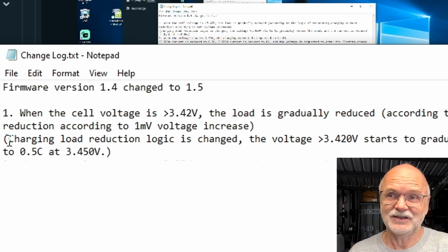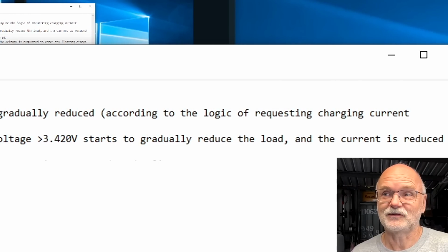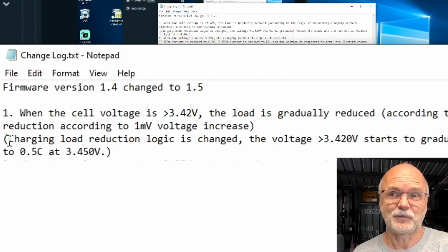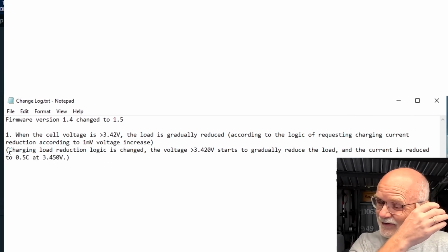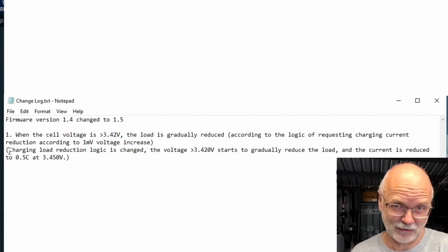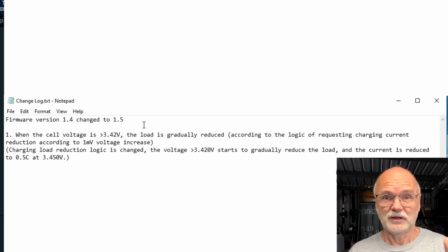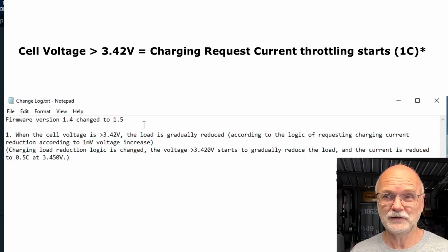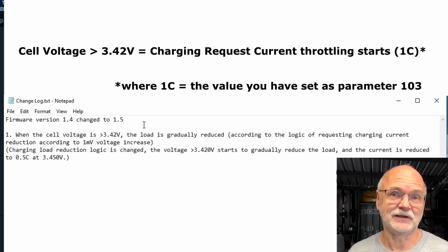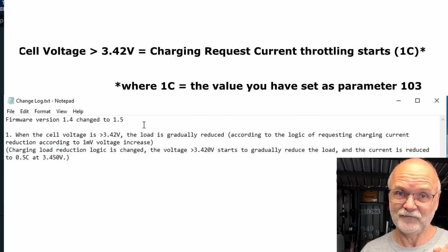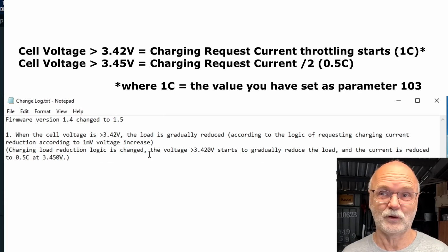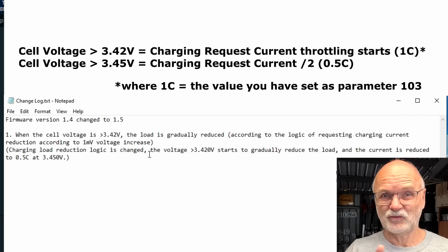Okay, bear with me here. The charging load reduction logic is changed. When the voltage is larger than 3.42 volts, it starts to gradually reduce the load, and the current is reduced to 0.5C at 3.45 volts. So what they're talking about is reducing the charge current into your battery - it's not about the load, this is about charging the battery. So if one cell hits 3.42 volts, they start reducing the charge current into the battery, at least requesting it from your inverter. And once a cell has hit 3.45 volts, the charging current is limited to 0.5C - it goes from the maximum all the way down to 0.5C.